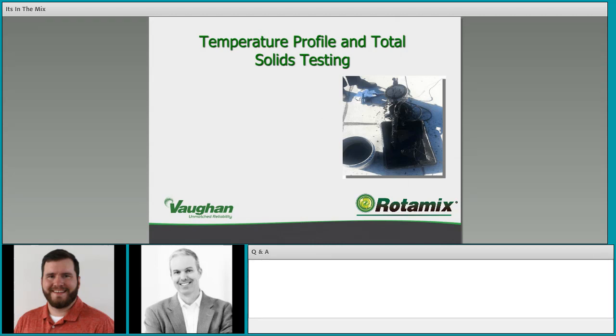Let's talk a little bit about validation in the next couple slides. We recommend doing the CFD on the front end to make sure that you're designing the system appropriately, and then on the back end you need to verify that the design is operating as required. Temperature profile and total solids testing are our recommendation for the best of both worlds in terms of having that validation.